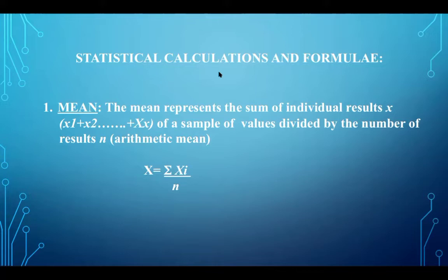Suppose manufacturer mean is 100, standard deviation is 2, our mean should be between 98 to 102, and our standard deviation shall not be wider than 2. So that way we develop objectivity in our system. This is what we are accepting.